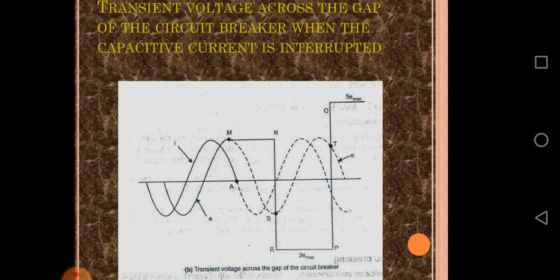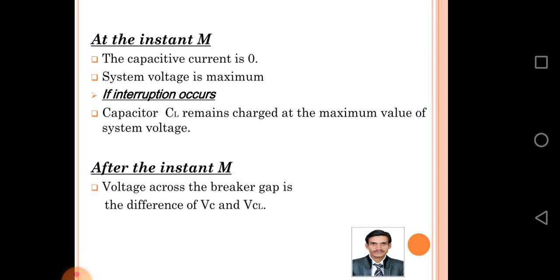This waveform shows the transient voltage across the gap of the circuit breaker when the capacitive current is interrupted. According to the waveform, the capacitive current is zero and the system voltage is maximum at instant M. If interruption occurs, capacitor Cl remains charged at the maximum value of system voltage.